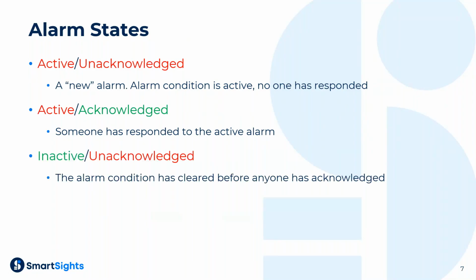Inactive unacknowledged means that the condition has returned to normal before anyone has acknowledged it. If that's actually true and the condition cleared on its own, that indicates maybe it's not actually an alarm as per the ISA definition, or perhaps the operator just never acknowledged it in the HMI system, though they did physically acknowledge it and respond in the real world. That can happen for a variety of reasons, due to a poor interface or the alarm occurring in the middle of a flood and them not understanding how to find it and acknowledge it on the screen. There are all kinds of logistical reasons why the alarm could end up in this state.